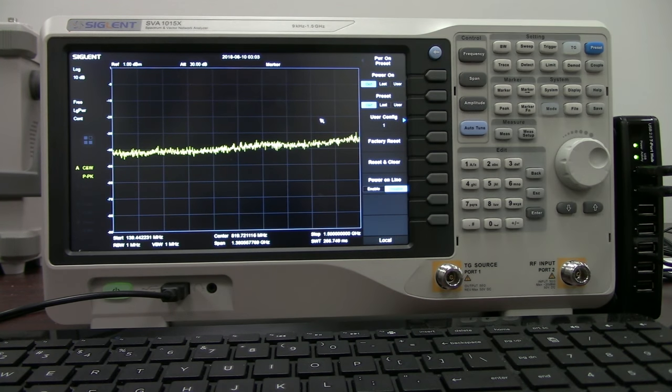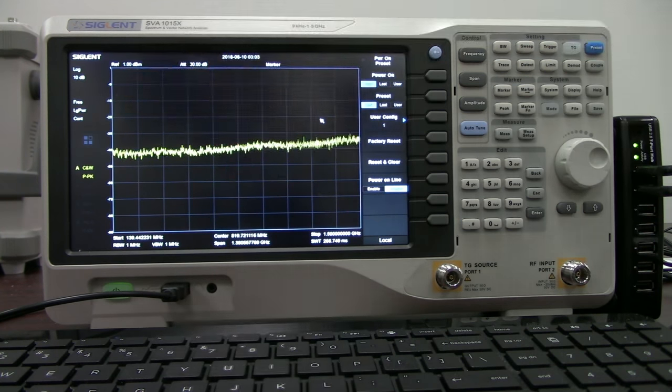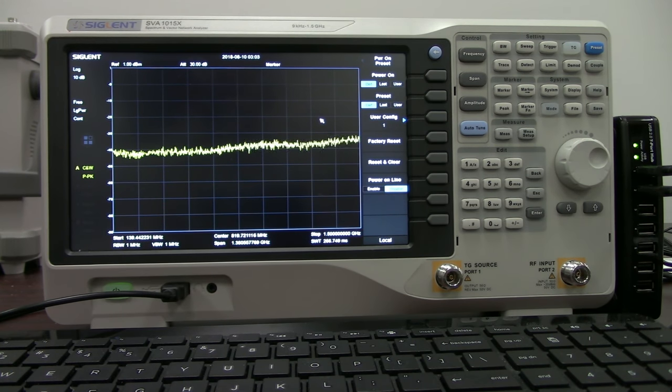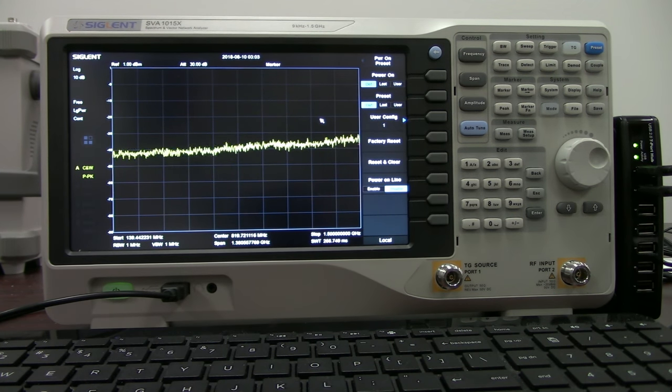In the default mode it says disable. If we were to disconnect the power from the instrument, what we would actually see is the instrument would not power on automatically. And I'm just going to briefly show you that by turning off the power strip to the instrument.